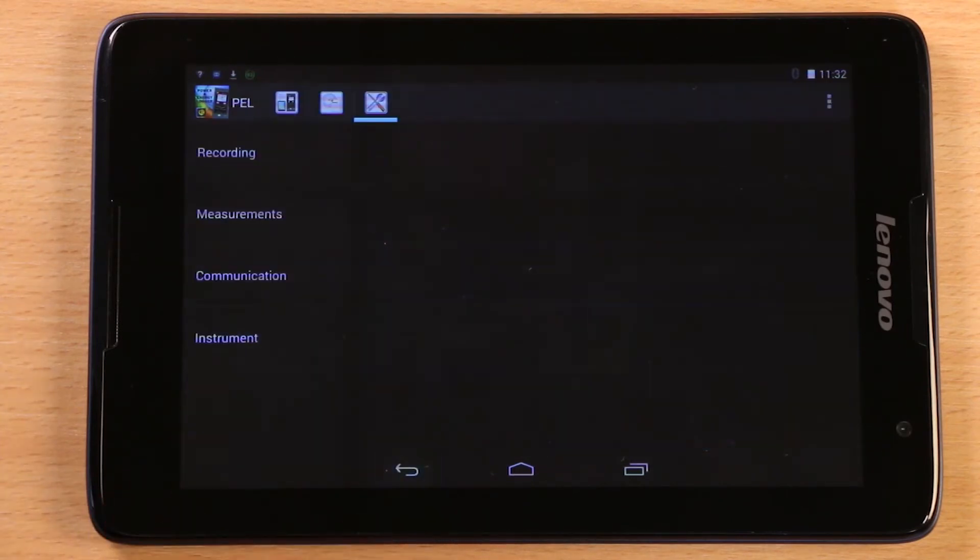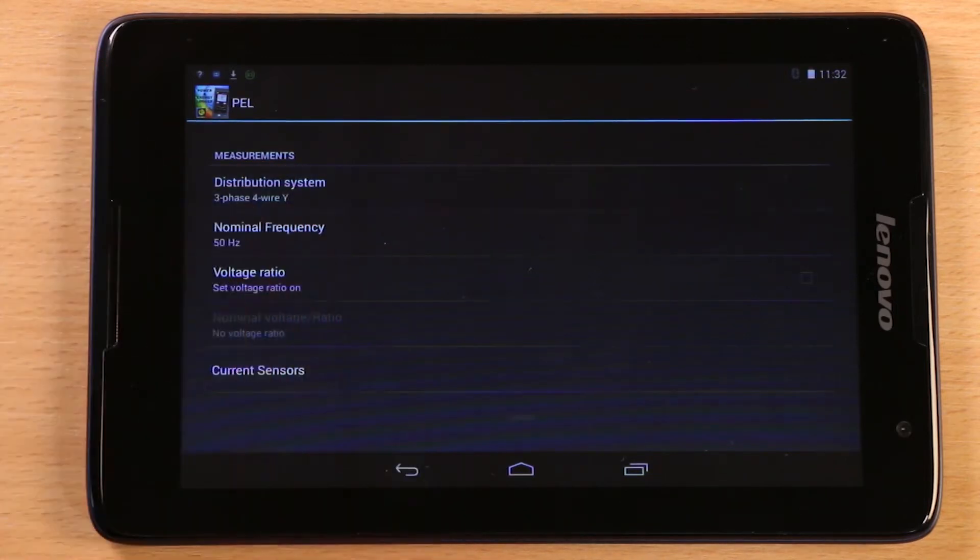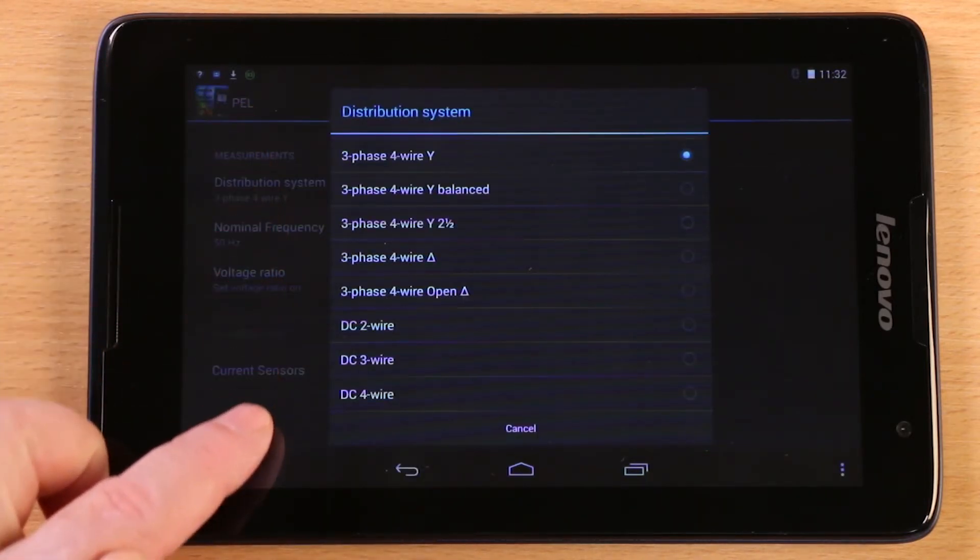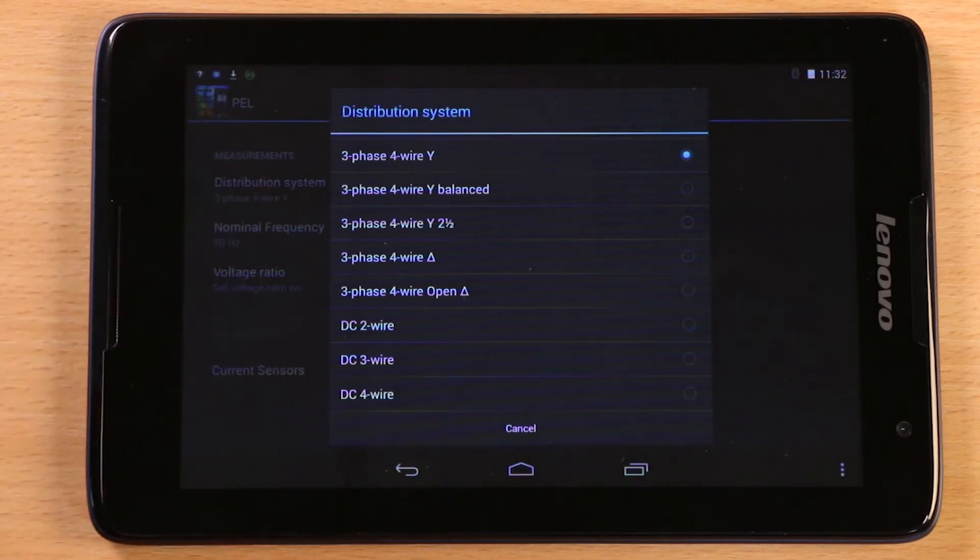Coming back a menu and selecting measurements takes you to this screen, where you tell the PEL about the installation you'll be connecting it to. Distribution system enables you to enter the nature of the supply, whether it's single phase or three phase, star or delta, even DC systems.